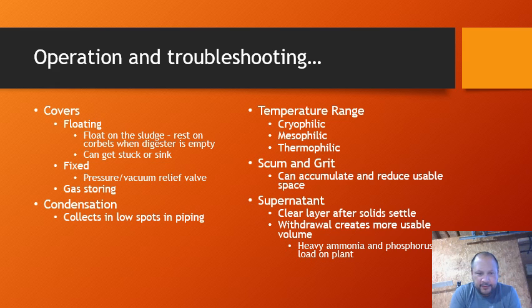Floating covers can occasionally get stuck. So that's a concern with the floating cover digester. Floating cover digesters also have been known to sink at times.